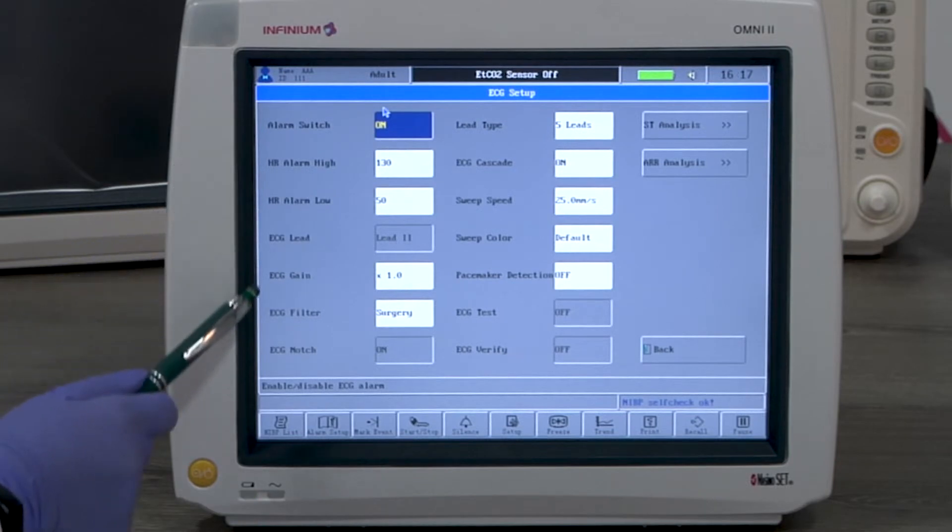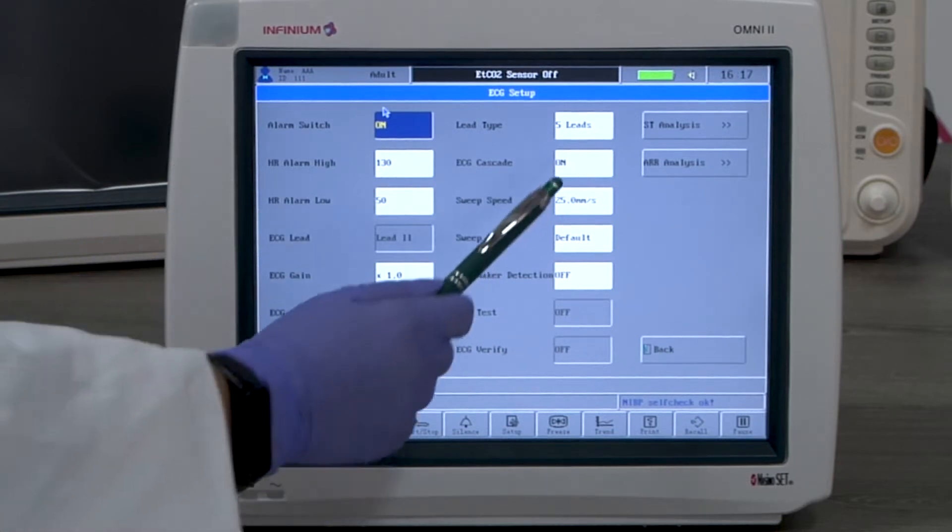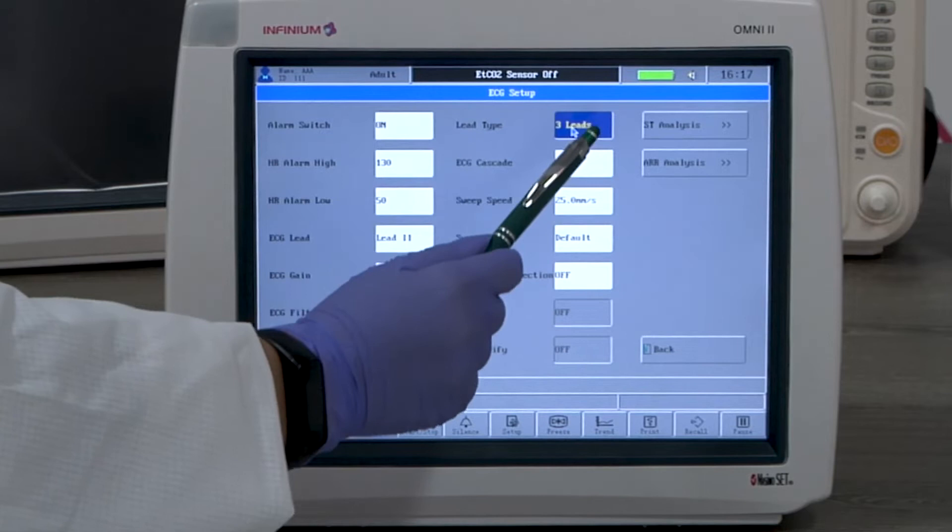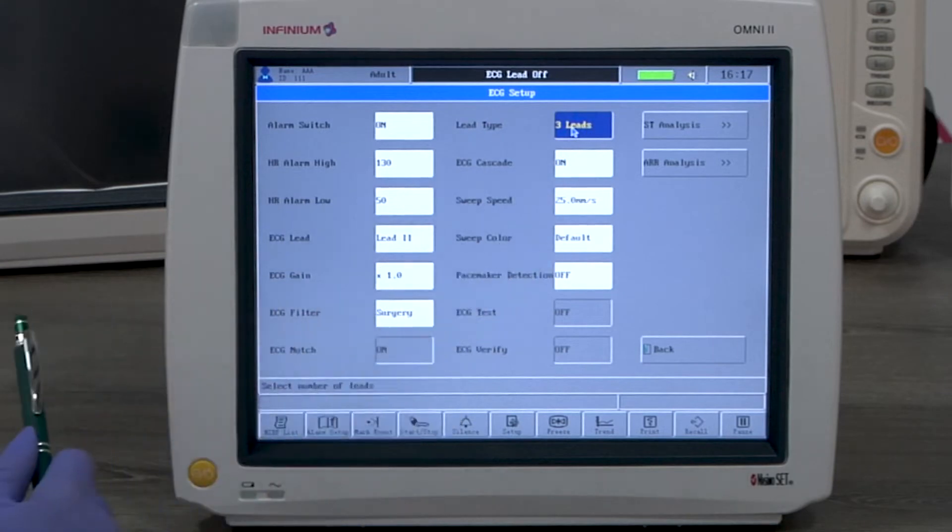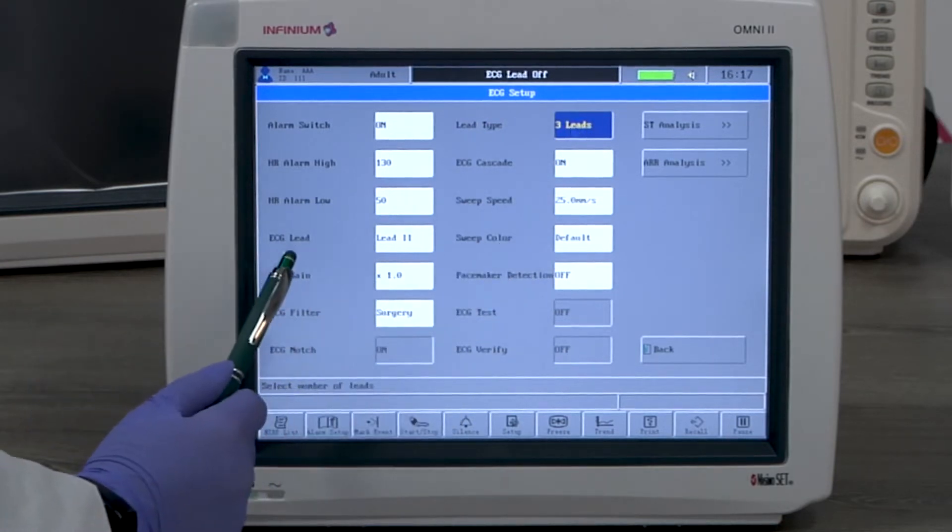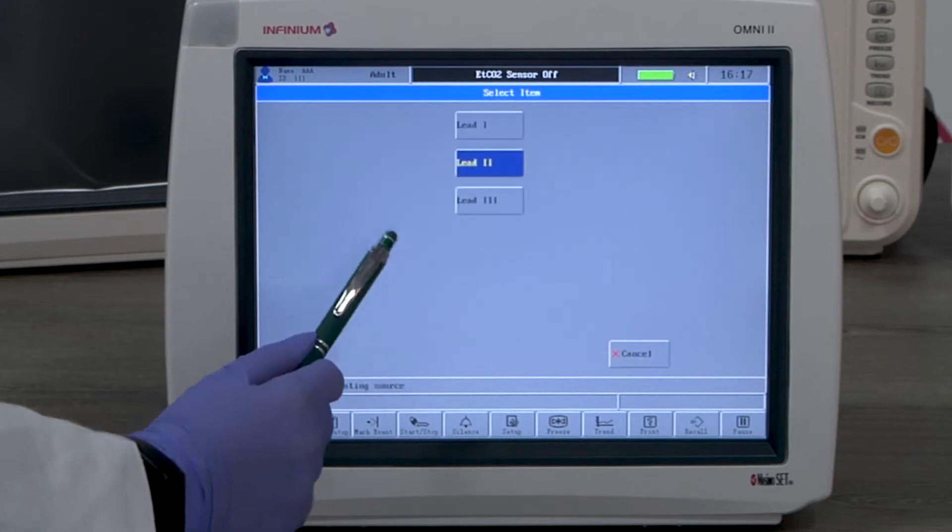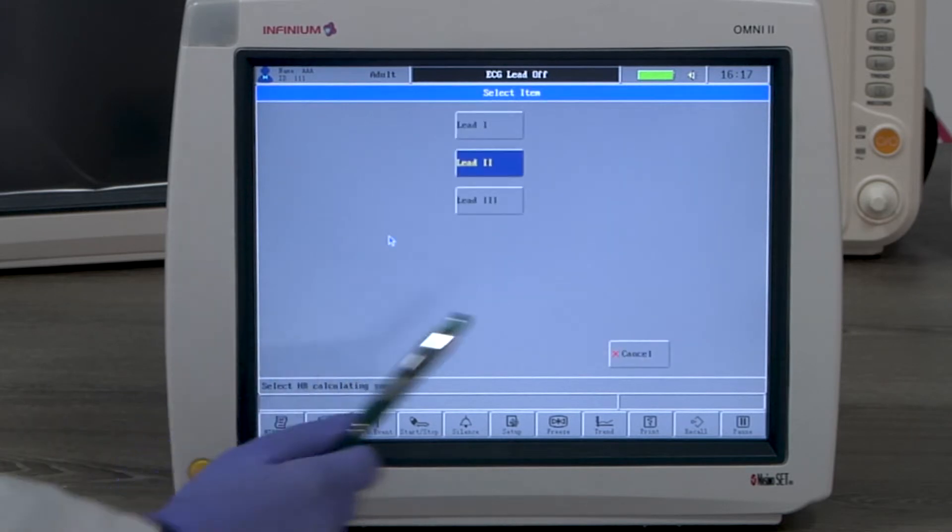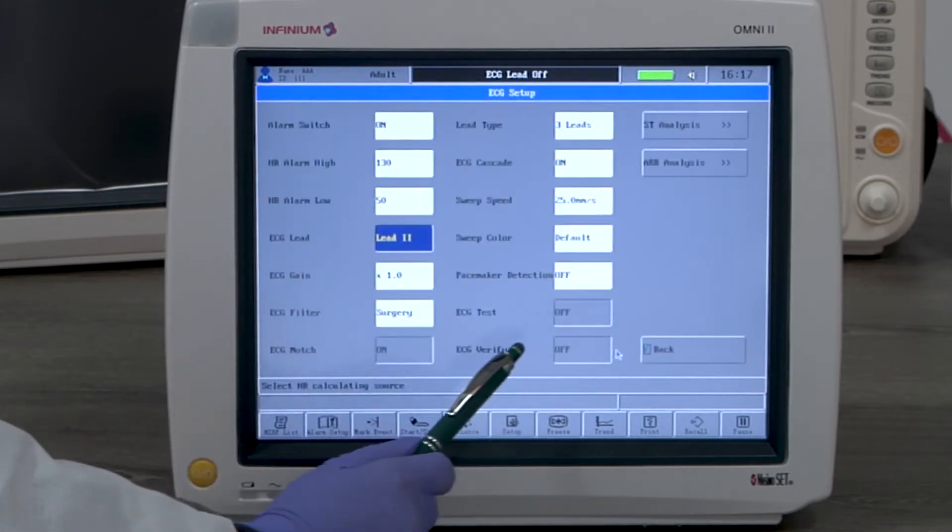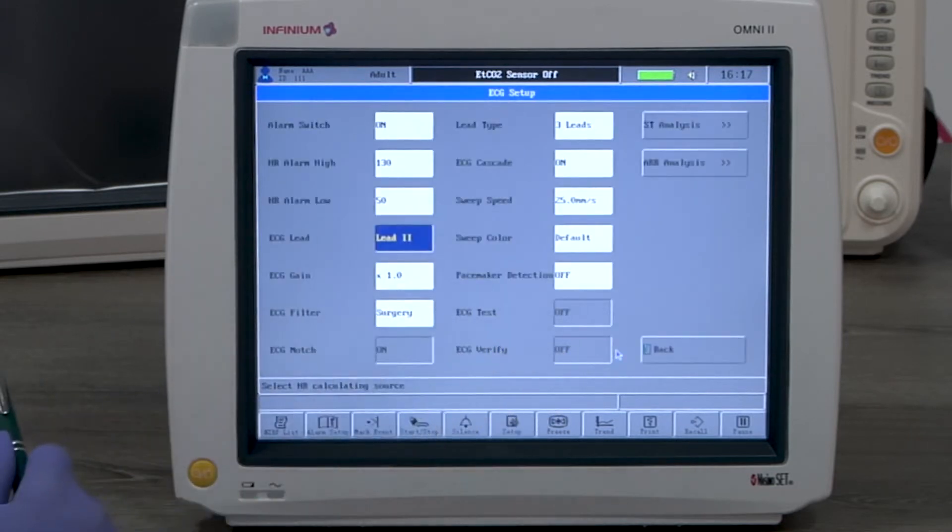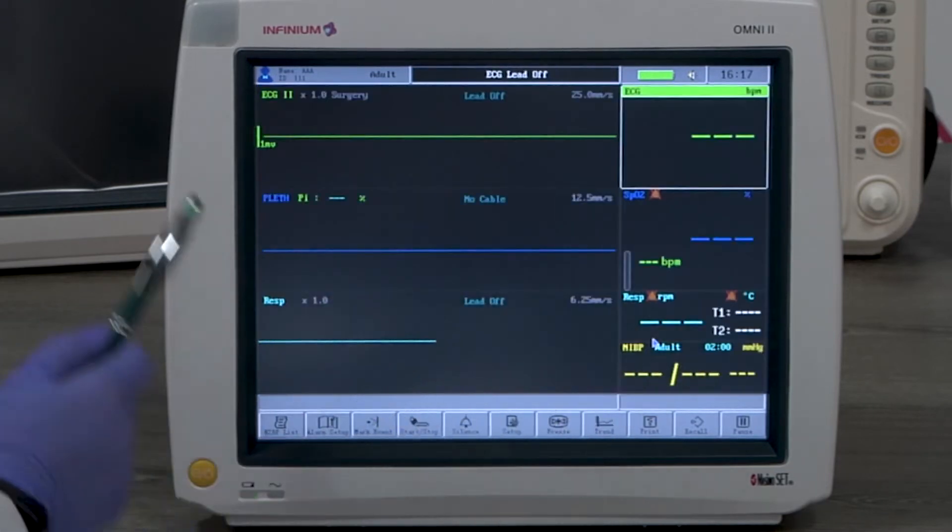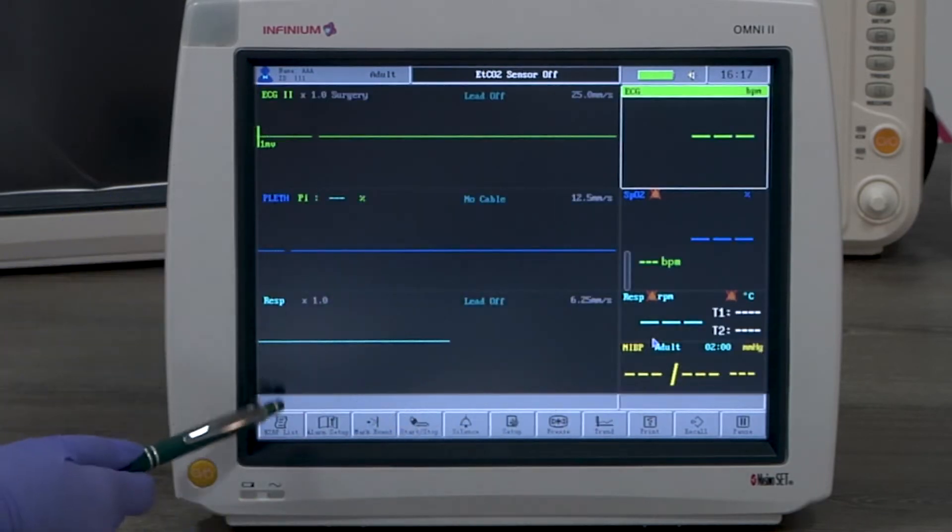The lead type option allows you to choose the ECG to be either 5-lead or 3-lead. When 3-lead is selected, the ECG lead option will be available for selection. Only the selected lead will be displayed. The display mode will also automatically be changed to a 3-channel display.